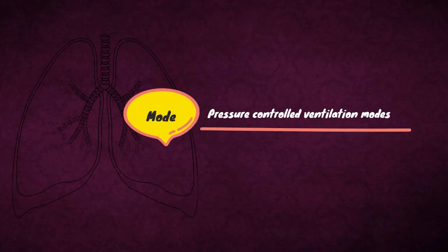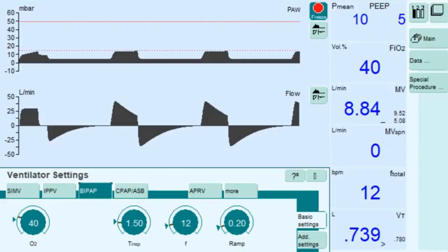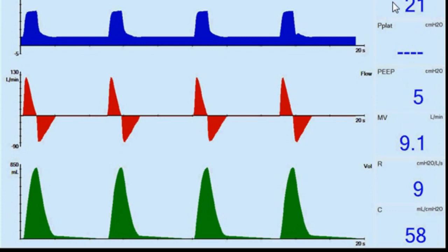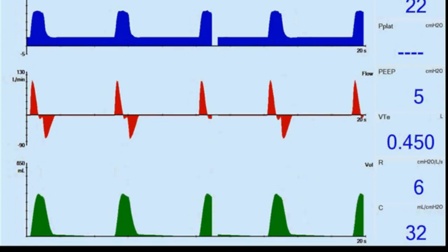Moving on to Pressure Controlled Ventilation Mode — Pressure Control Continuous Mandatory Ventilation. The tidal volume supplied to the patient depends on the pressure difference between PEEP and inspiratory pressure, the lung mechanics, and the breathing effort of the patient. The number of mandatory breaths is defined by the breathing frequency. The mandatory breaths are machine-triggered and not triggered by the patient.